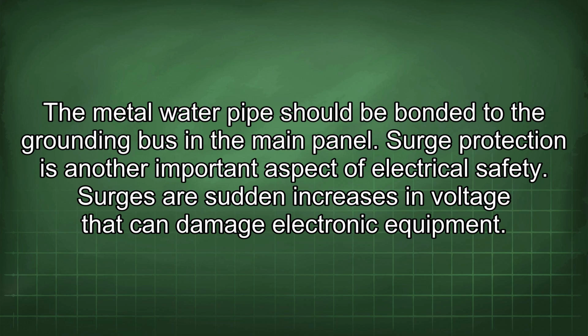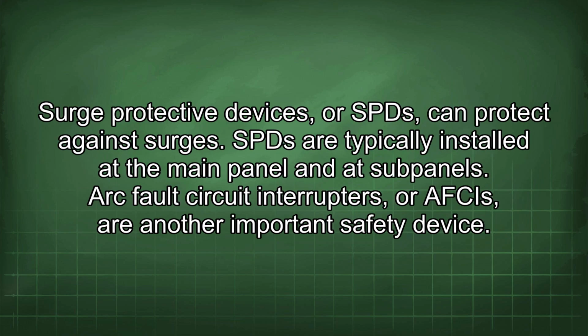Surge protection is another important aspect of electrical safety. Surges are sudden increases in voltage that can damage electronic equipment. Surge protective devices, or SPDs, can protect against surges. SPDs are typically installed at the main panel and at subpanels.